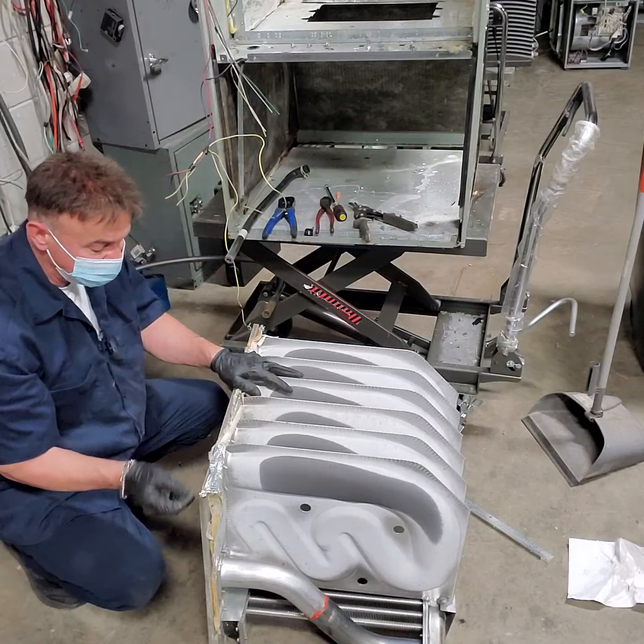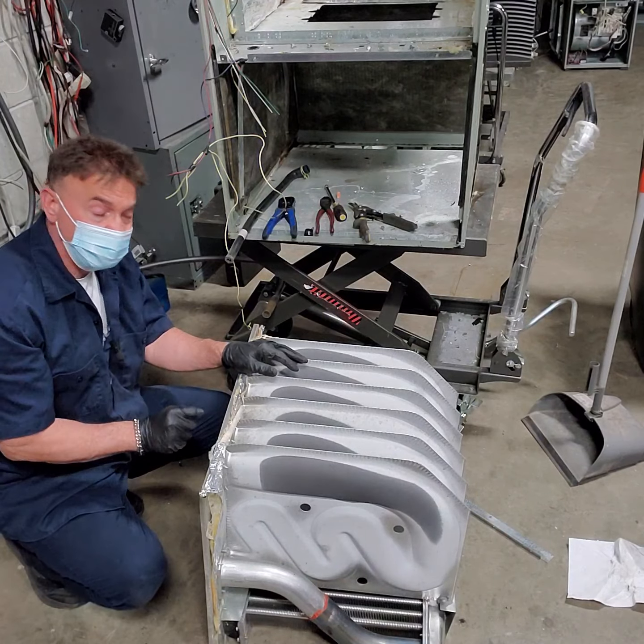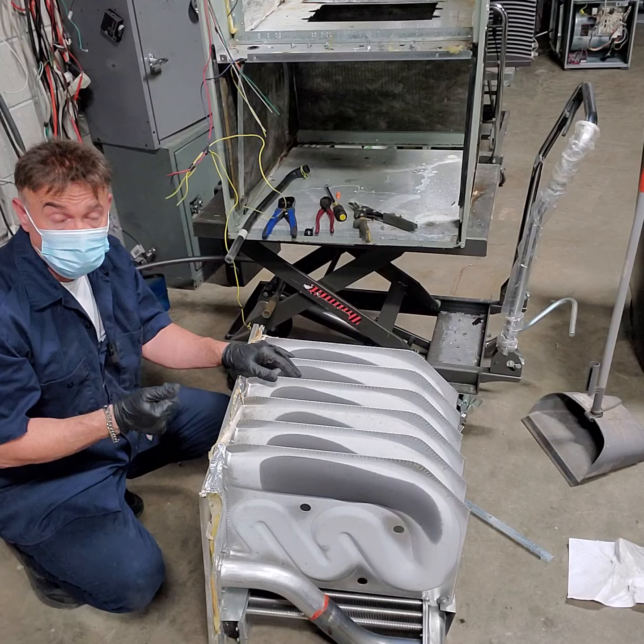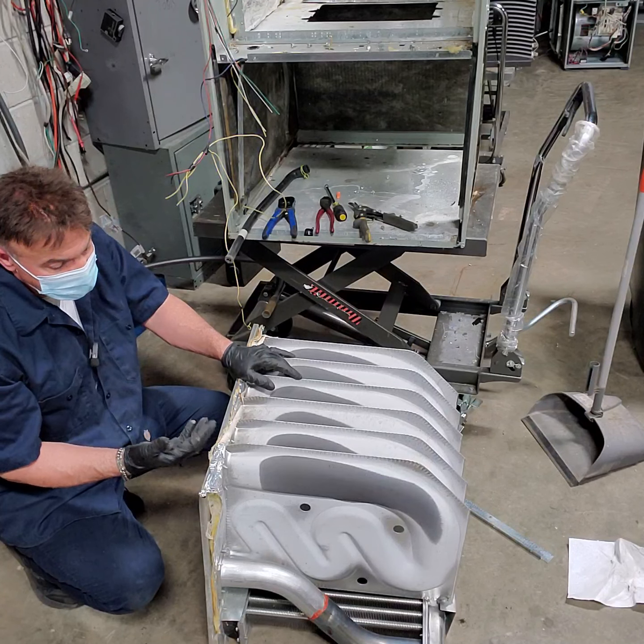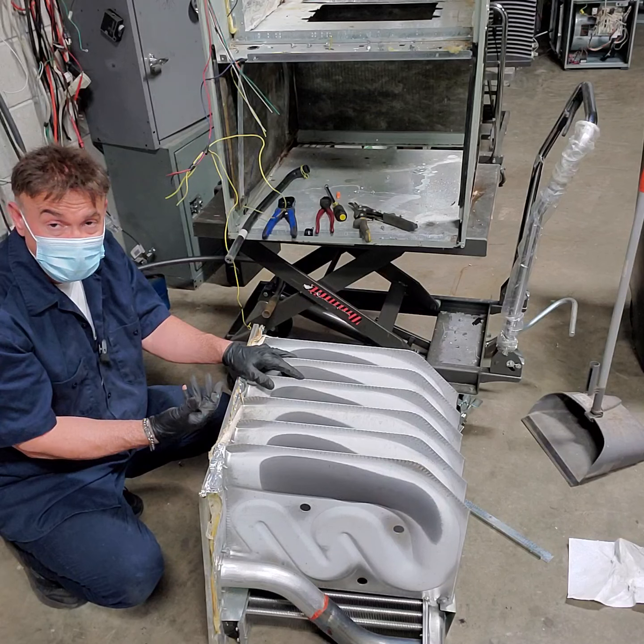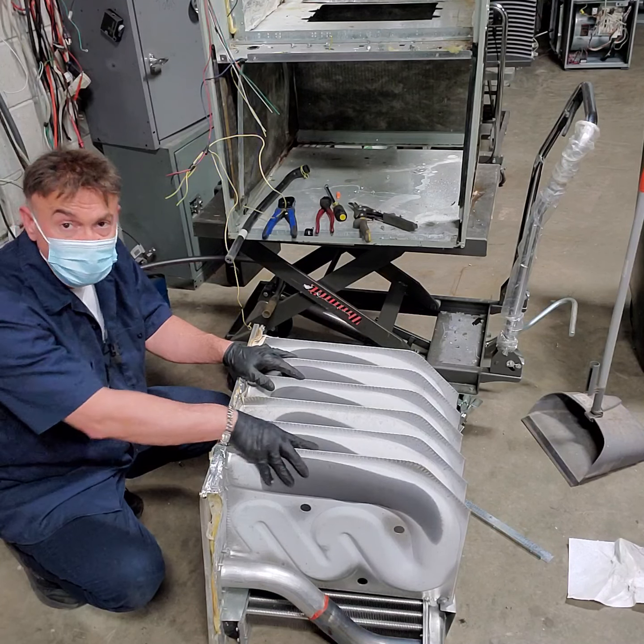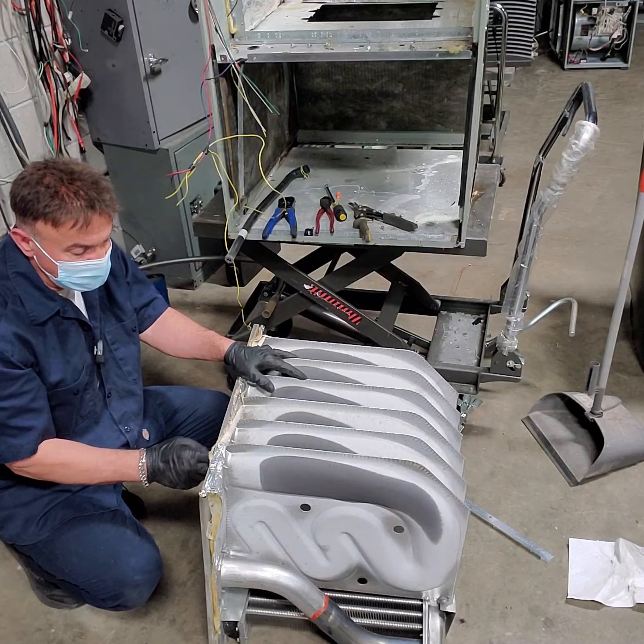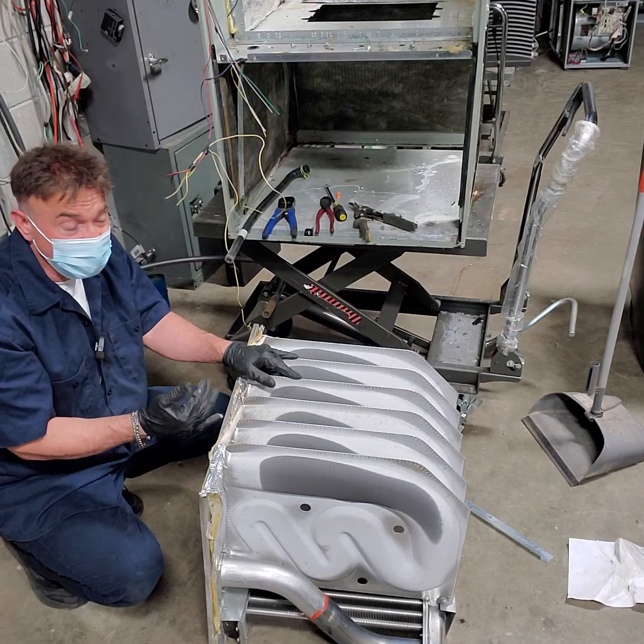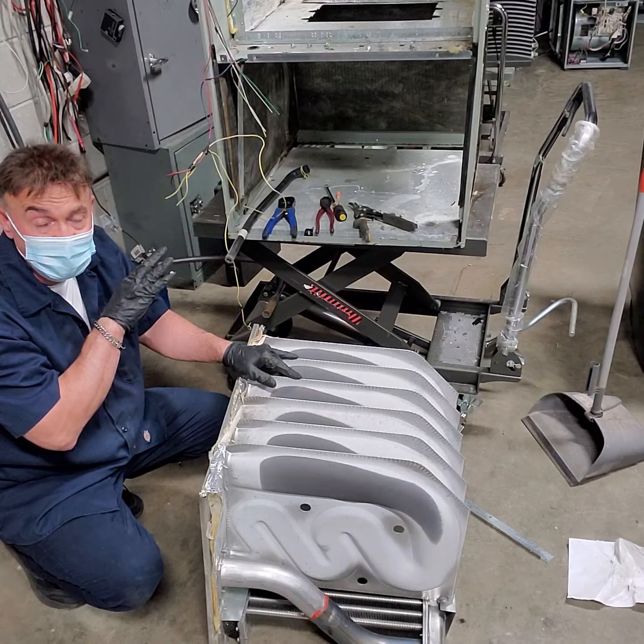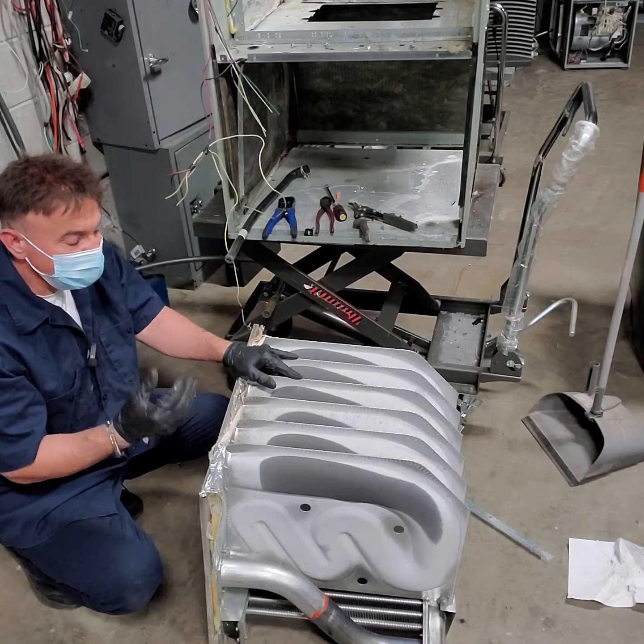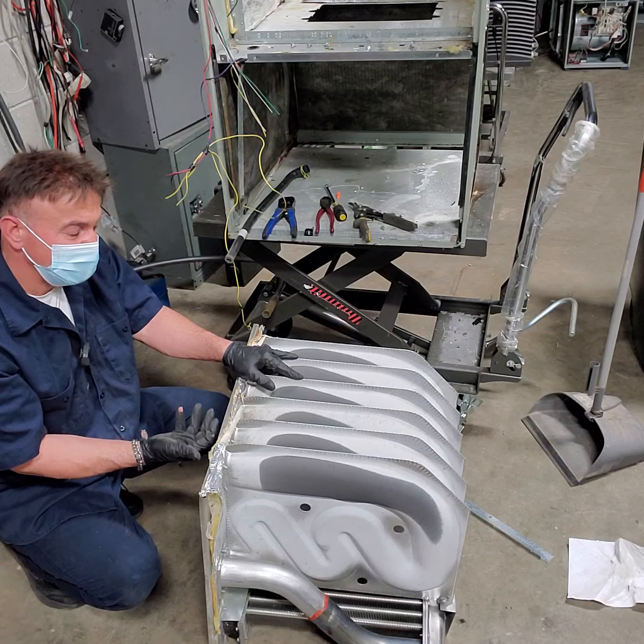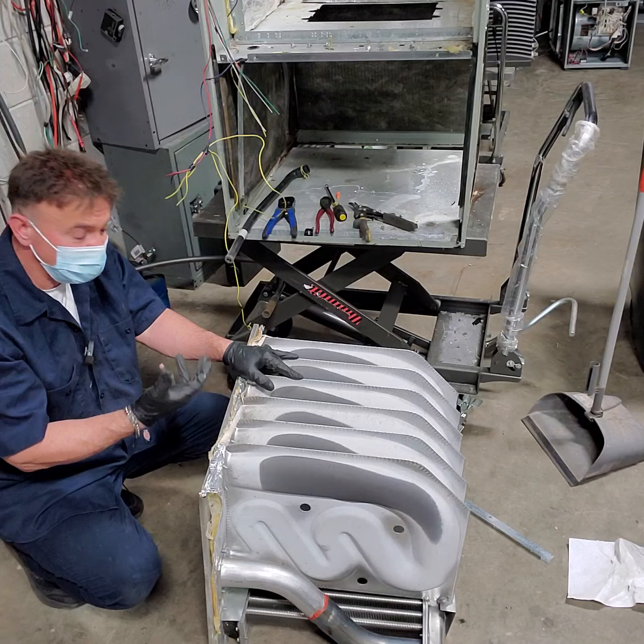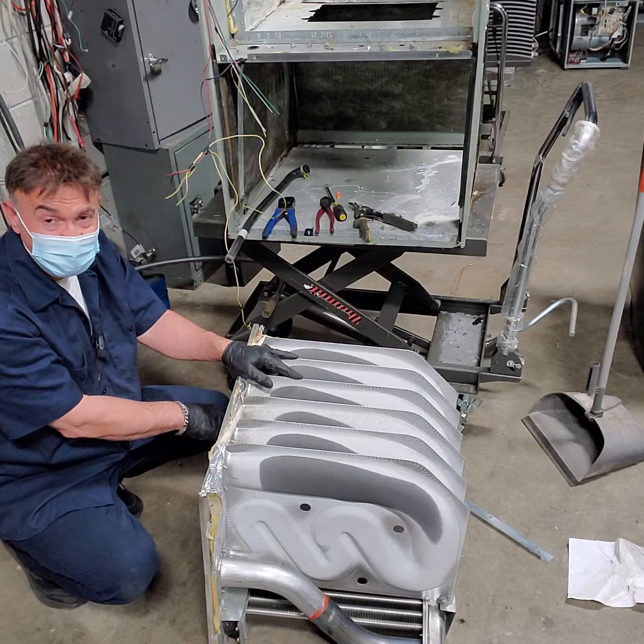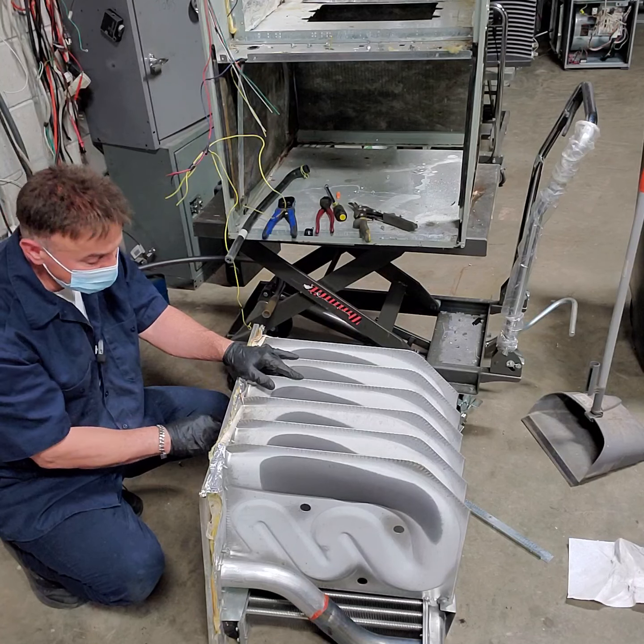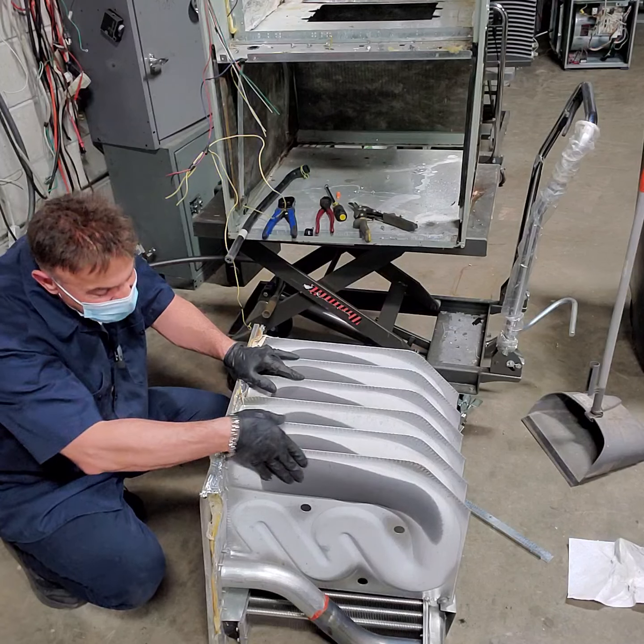Why is that? Because the burners were so strong, and no matter how strong the blower is running, it is not able to remove that heat 100%. It's not able to cool it. And the limit is not able to stop the system because the temperature was not getting to a really dangerous level. So what happened is the flame was too strong. The blower is trying so hard to remove the heat. The limit is not sensing a really dangerous temperature because there is some air coming through. But at the same time, this was frying.